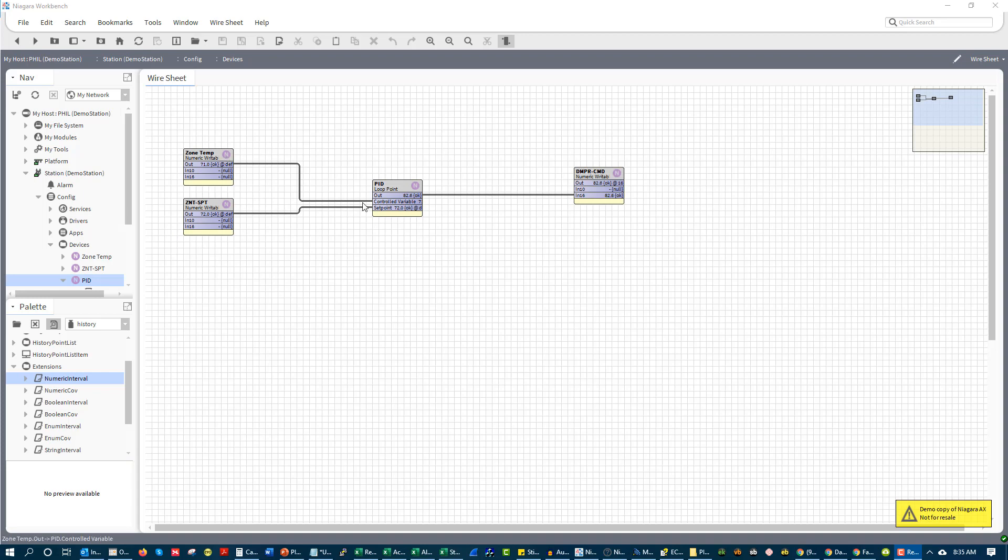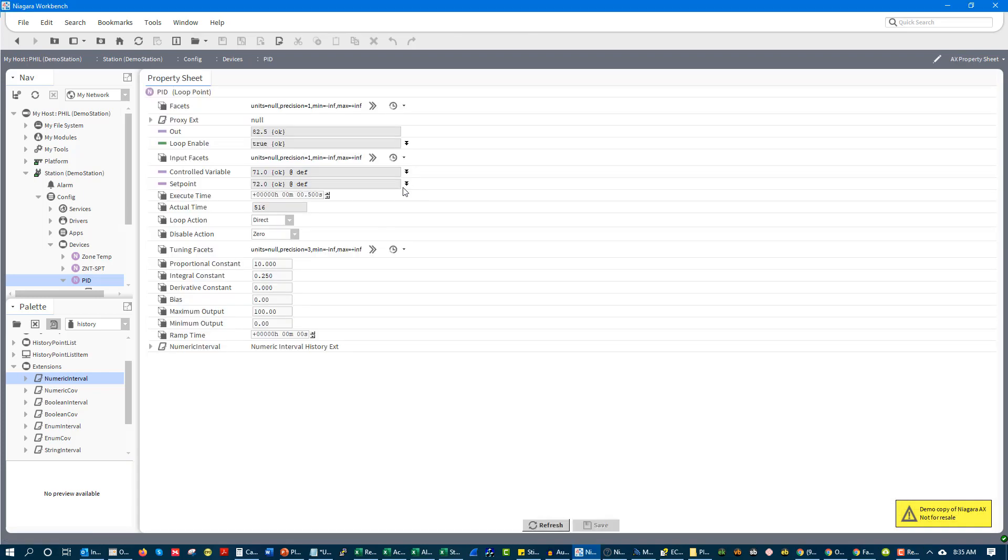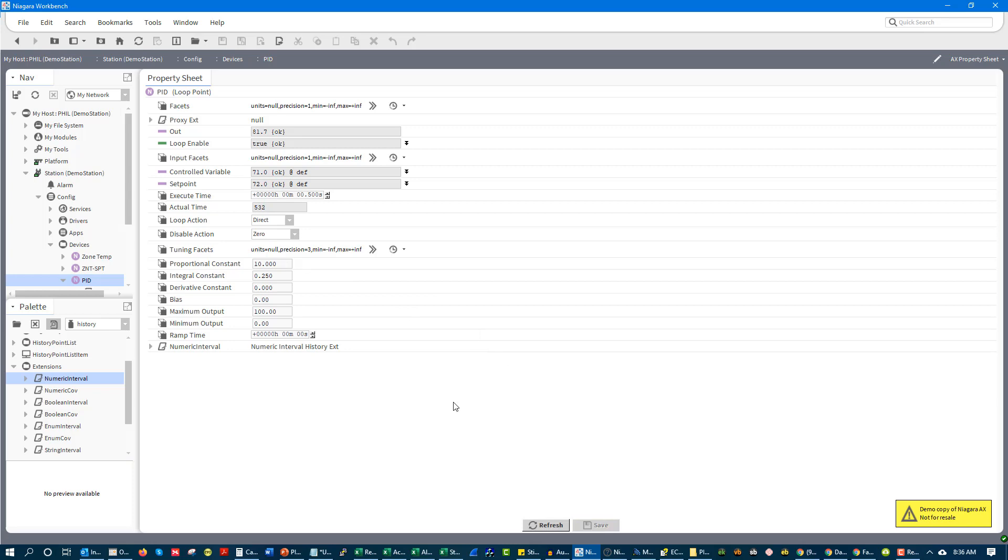So what happens is when this loop detects essentially what is called error, which is the difference between setpoint and process variable, then the first thing that happens is you have a proportional response. So what you look at is the sensor span, essentially the controlled range of the sensor.